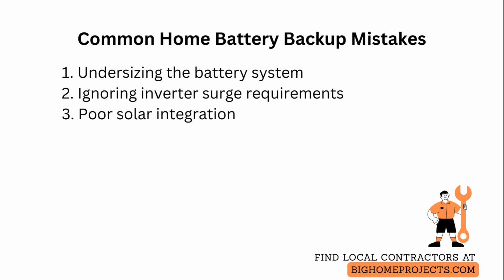Common mistakes include undersizing the battery, which leads to rapid depletion during extended outages and user frustration. Solve this by calculating realistic outage scenarios and adding at least 20% capacity margin. Another issue is neglecting inverter surge and motor start requirements, which causes systems to trip during appliance startup. Mitigate this by sizing inverters to handle surge currents or shifting large motor loads to non-critical circuits.